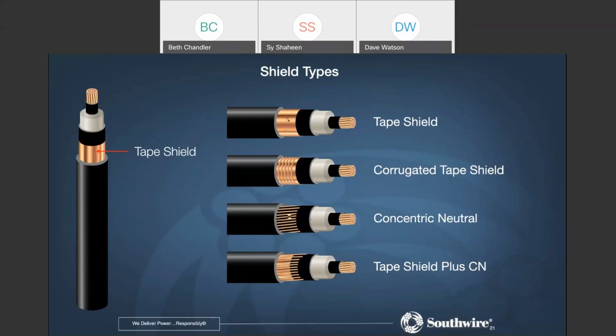The tape shield is usually used in a three-phase application. For instance, you're going from the switch house, which is outside your data center, and you take the power up to your switchgear. Now you're inside the protective area, where you have to go through a turnstile into the data center. So now you can use this tape shield, which is there to bleed off the electrostatic charge. It cannot handle neutral currents, but again, you're going from the switch yard to, let's say, your big transformer, 25 MVA or what have you.